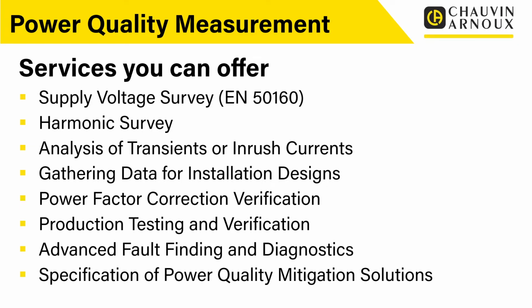It's automated, it's set up, it's a standard report in there that you can do. So this is monitoring the supply voltage, the limits, the ups, the downs, the surges, the swells, the sags, all that sort of stuff. And again, that's all quantified within EN 50160. So an EN 50160 survey is a standard service that you can offer. And if you look online, people are offering those surveys.